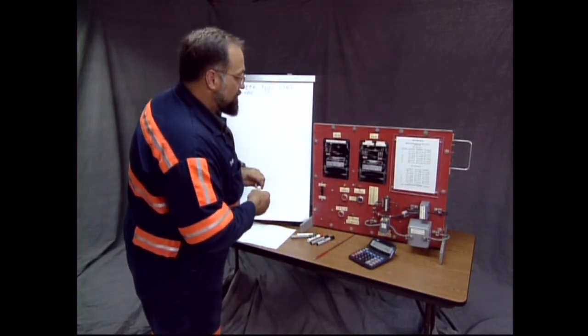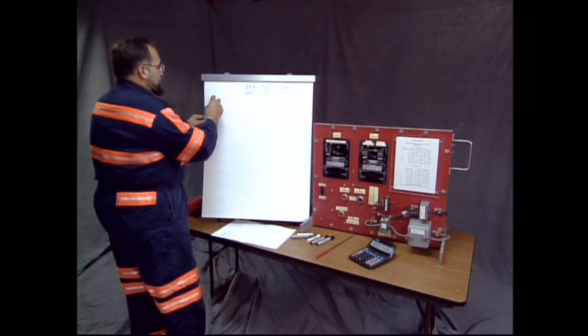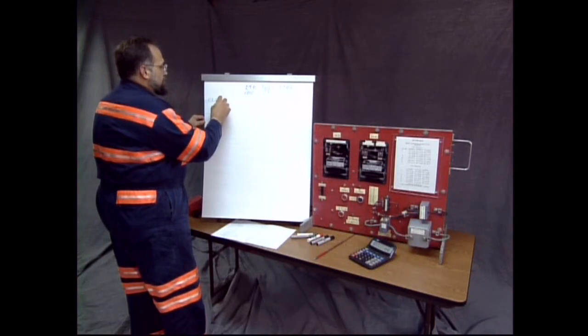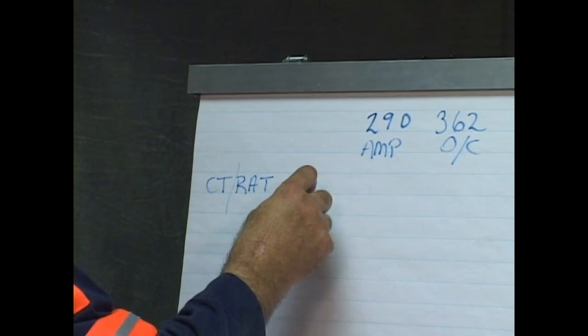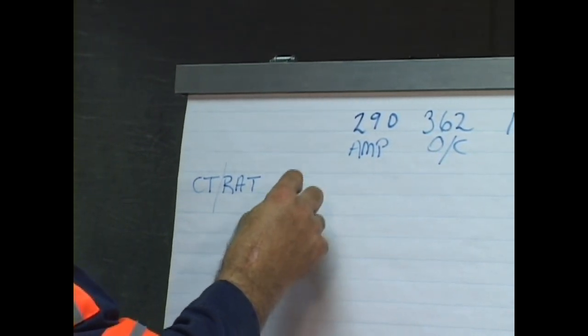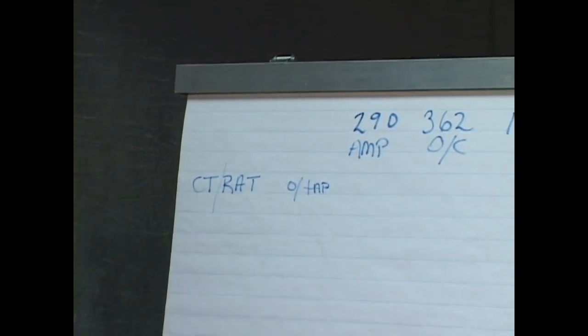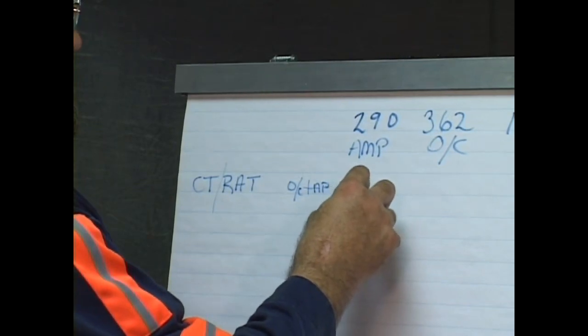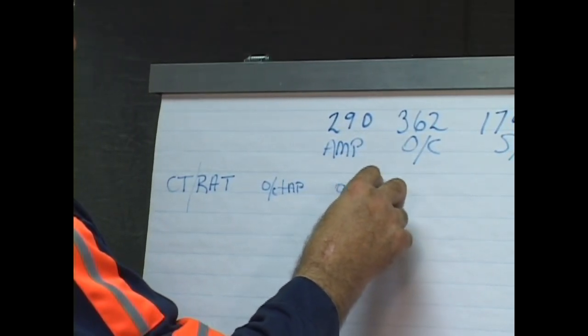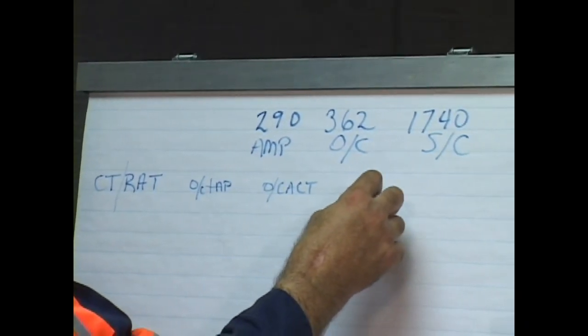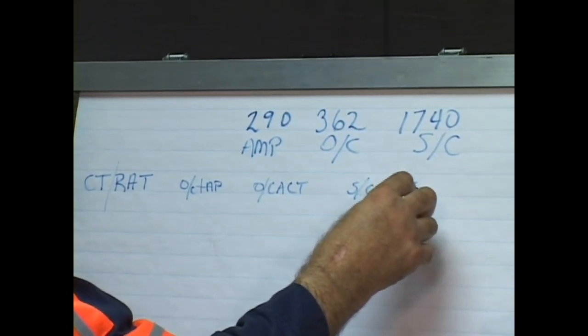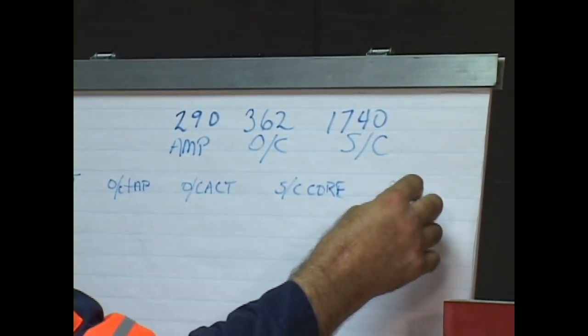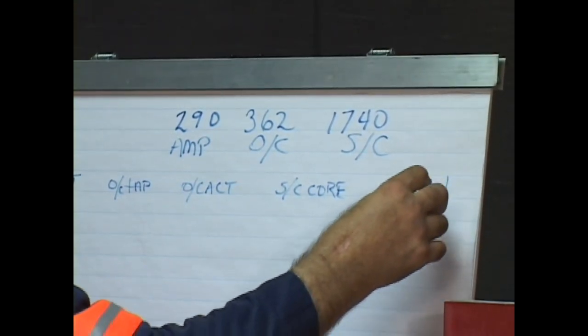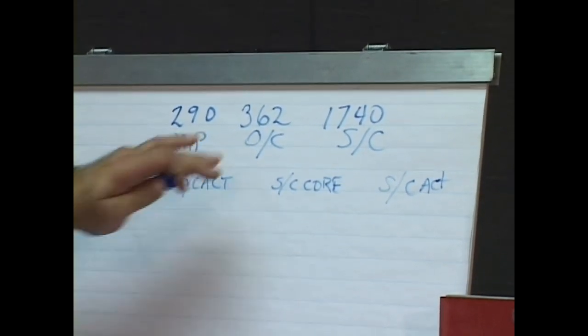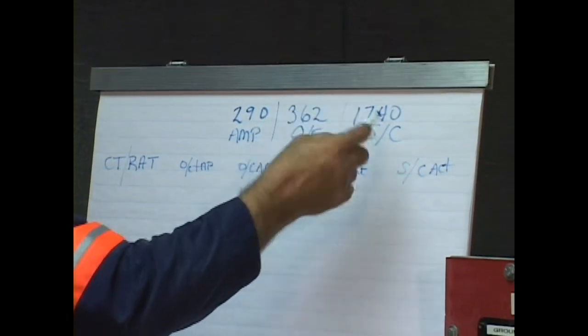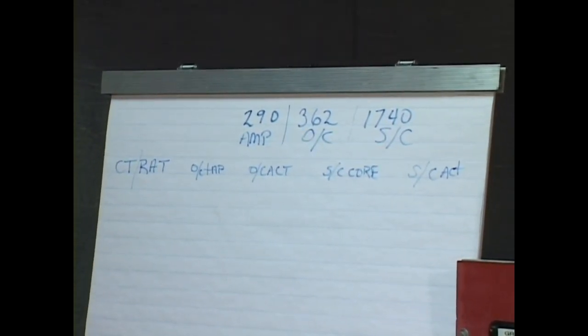Now, first thing that you're going to do to compute this, you need to have your CT ratio. Let's call that CT ratio right there. And then you're going to have an overcurrent tap. You're going to have overcurrent actual. You're going to have a short circuit. That's determined with a core. And you'll have a short circuit actual. Okay. Now our goal is to come as close to these numbers as we can without being excessive, without exceeding those maximum settings. Here we go.